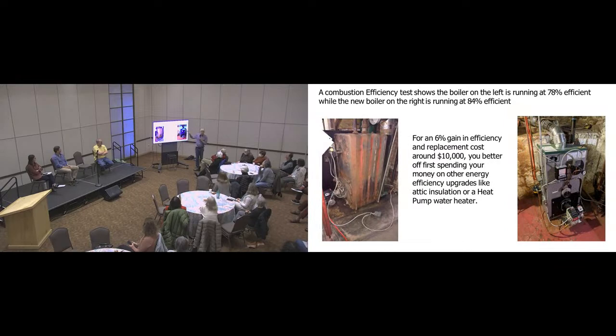If you run a combustion efficiency test on a boiler, you can see really how well it's doing. This boiler, even though it's horrendously ugly, was running at 78% efficient. This much newer boiler was running at 84% efficient—so that's a 6% gain. I think ultimately, if you're going to stay with oil, yes, you might want to replace it. But before you spend that $10,000 to replace this, put all that money into insulation instead.